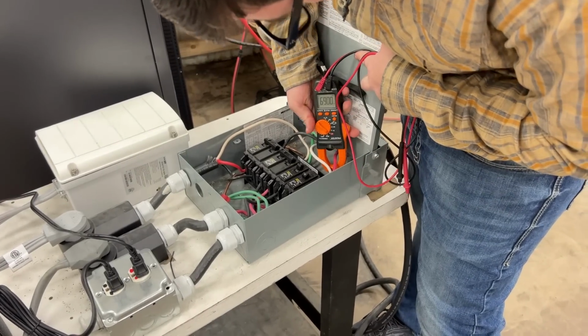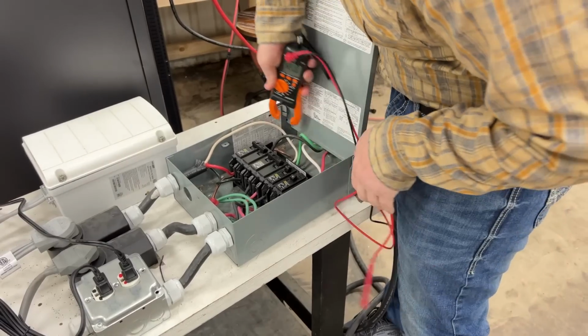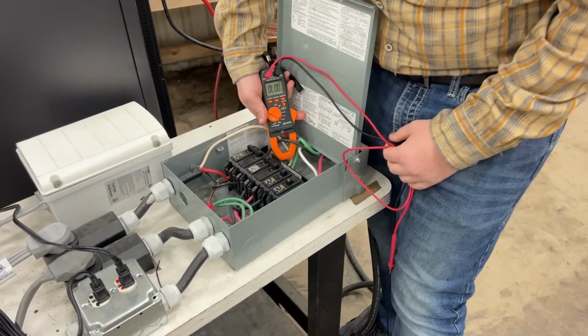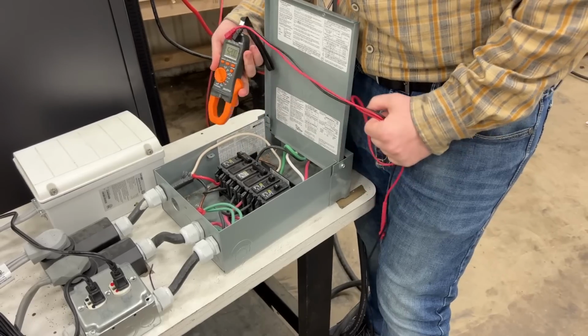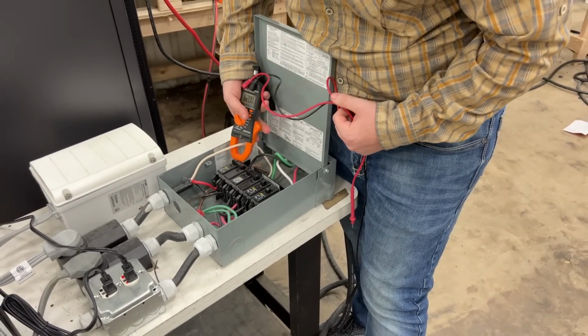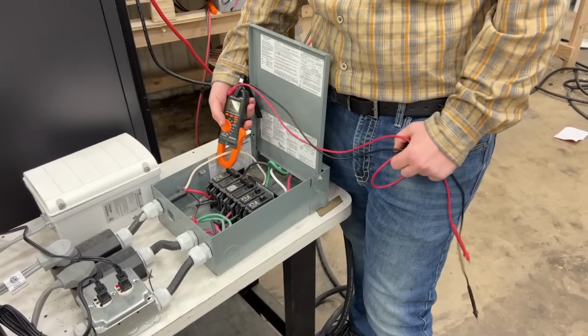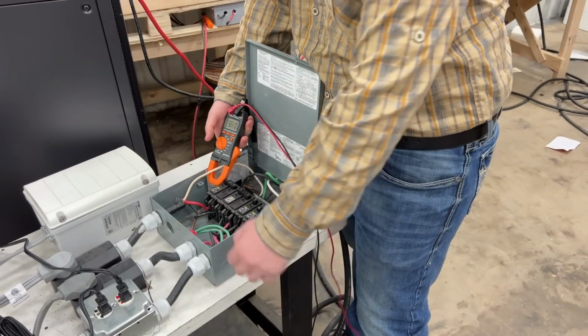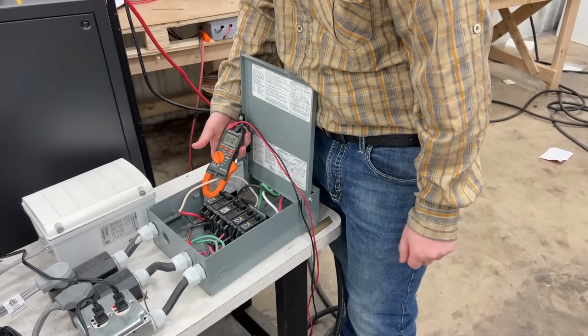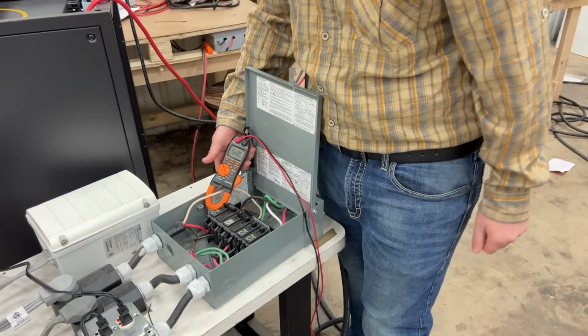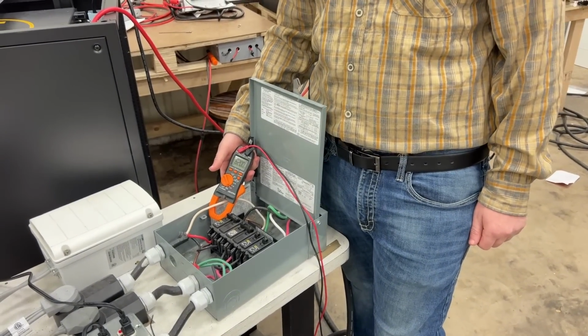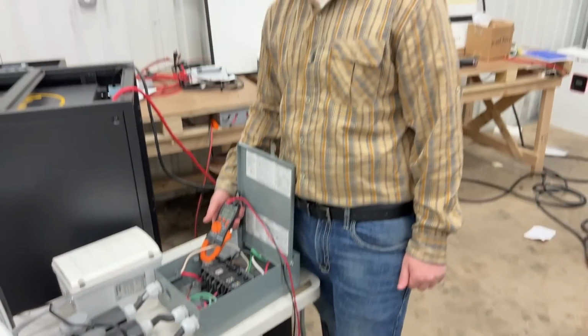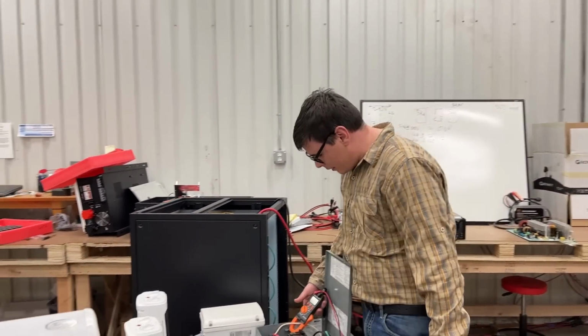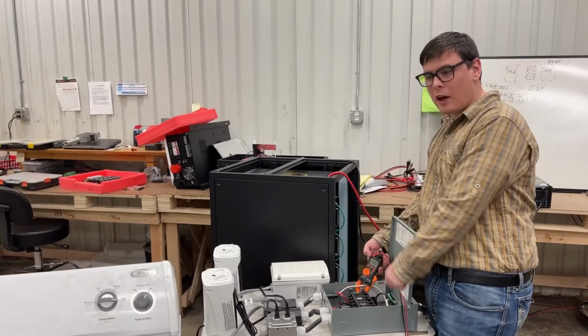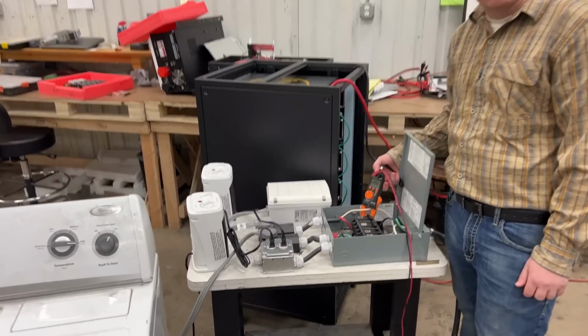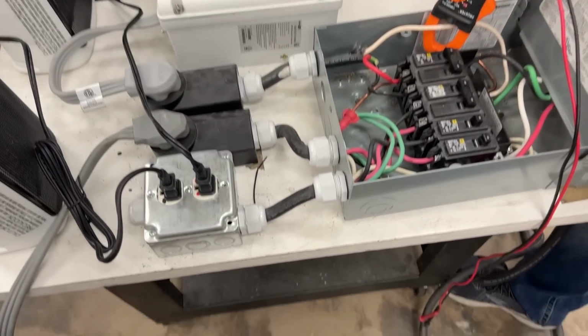Second here, it's ramping up. I got 7 amps on line 1, on line 2, and I'm up to 7 amps. So that's 14 amps, okay? So 14 amps in, and my return current here is 14 amps. Now, what happens when I turn the other heater on? What do you know? It goes down. The transformer is working less right now. We added another 14 and 2 identical heaters. I am pulling 0 watts from the transformer, running 2 heaters because I balanced them.